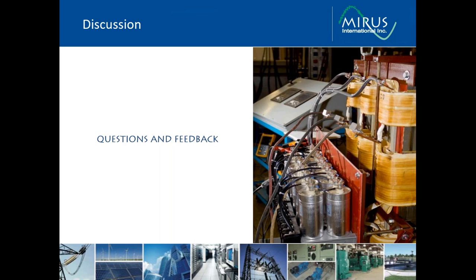What impact does the DC bus capacitance have on input harmonic and system resonance? The DC bus capacitance doesn't typically introduce a problem with resonance on the power system side. The power system resonance is typically the result of the harmonics being interjected by the variable speed drives and the power system resonance. So if you have a filter, the filter capacitor banks are much larger than a DC bus capacitor bank, so it will have an effect. If you have power factor correction capacitors, I don't see a big issue related to the DC bus capacitance and system resonance.